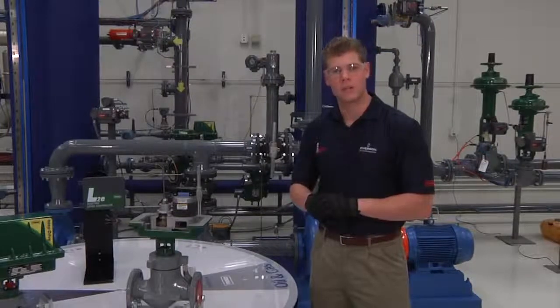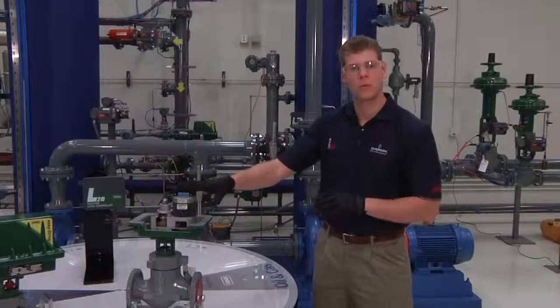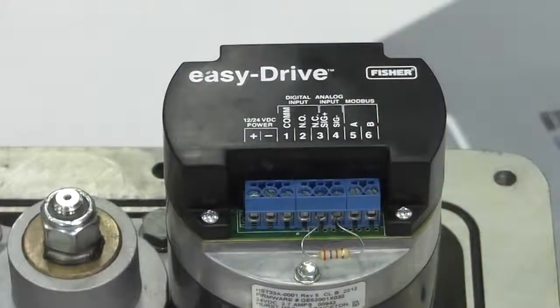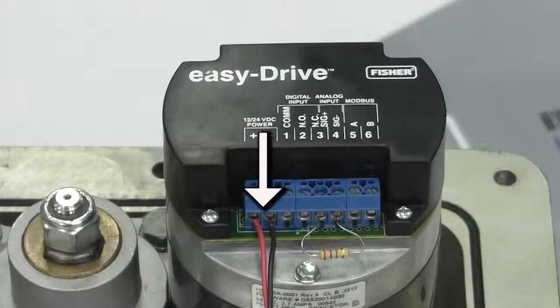First, we will wire the positioning version of the Easy Drive on the D4 valve assembly. As you can see, each terminal on the terminal cap has been labeled for convenience. Note that the power is polarity sensitive, therefore make sure that the power cabling has been properly installed and grounded before attempting to power the actuator.